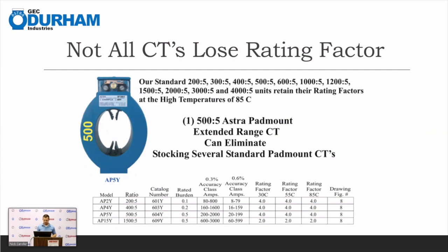Yeah, that is typically the experience. However, there are some CTs that do not derate. So the GEC Durham Astra extended range transformers, as you'll see in our chart here, do not derate at 85C. It does retain its rating factor. Excellent. This is one of the exceptions to the rules, and a very popular transformer as well.